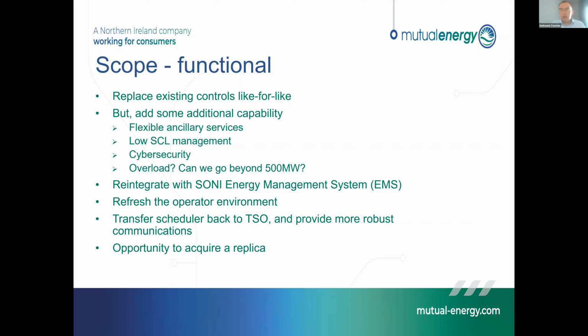One of the key things is integrating with SONI's energy management system. As Sam said, they've had SCADA upgrades in the meantime that have meant that that previous functionality has been lost. It gives a complete refresher of the HMIs, the operator environment, and allows us to design the screens to be as user-friendly as possible for what we need today and for the next 15-20 years. It puts a transfer scheduler back to the TSO, and there's more robust comms infrastructure being put in place as part of this project. And it also gives the opportunity to acquire a replica. So we go to the next page.